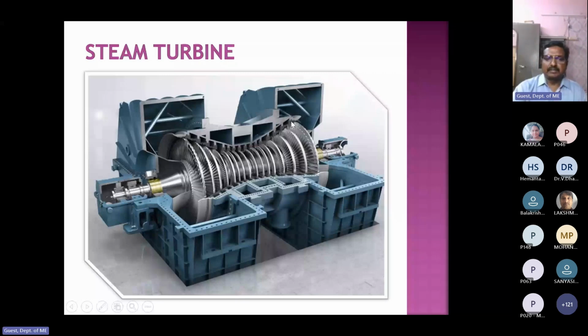In this turbine, steam enters at the center and flows in both directions. That is why it is called a double flow turbine. The double flow turbine has steam flowing in both directions, so there is no problem with the balancing of the turbine. So it is a shaft, and this total shaft is taken by the two bearings. There are two bearings mounted on either side of the shaft.